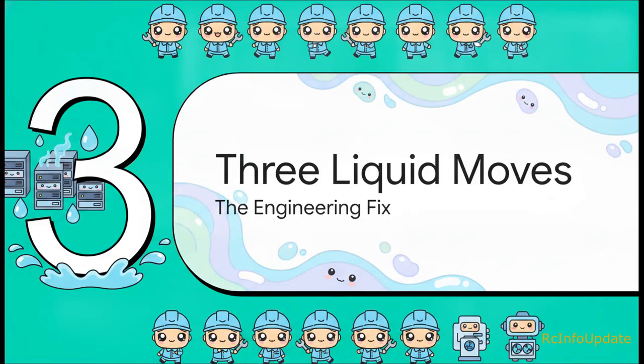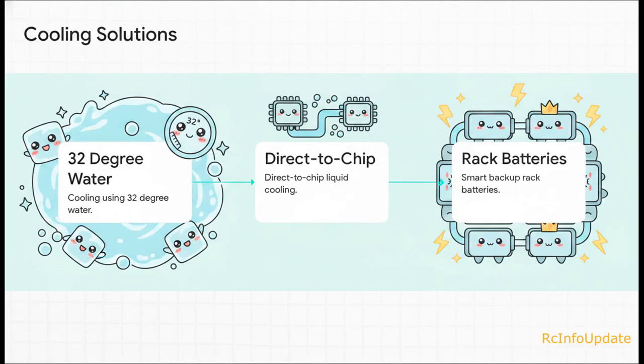But hey, don't panic. Part three, the three liquid moves, the engineering fix. Brilliant engineers are rolling out specific rescue strategies right now to stop these meltdowns before they happen. Basically, three physical moves are saving the day here: number one, using 32-degree water; number two, pumping direct-to-chip liquid cooling; and number three, installing smart rack batteries. These three steps absolutely change the game.